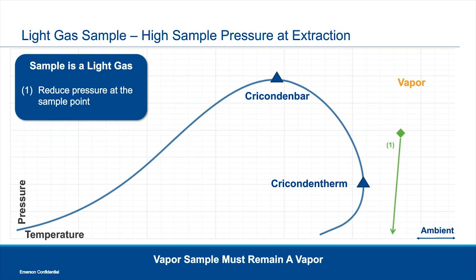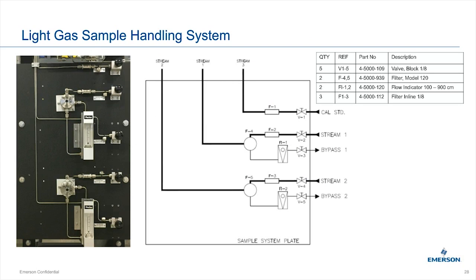For a light gas, it's one of the easiest sample systems to design. You're in the vapor phase and not particularly close to the phase curve, so you can strictly do pressure reduction without worrying about hydrocarbon dropout. A typical sample handling system for this case includes a 2-micron filter and membrane filter, keeping with the five principles of removing contaminants and free liquids. A bypass with flow indicator is recommended to maintain differential pressure and continuously sweep free liquids out.